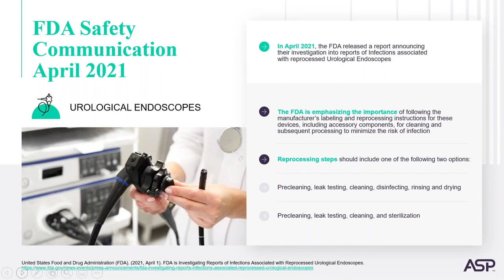The FDA is emphasizing the importance of following the manufacturer's labeling and reprocessing instructions for these devices, including accessory components for cleaning and subsequent processing to minimize the risk of infection. Reprocessing includes either pre-cleaning, leak testing, cleaning, disinfecting, rinsing, and drying, or in other words, high-level disinfection, or pre-cleaning, leak testing, cleaning, and sterilization. Are you following all these steps in your urological endoscopes? Is the process complete from the procedural area or the operating room through the reprocessing area?